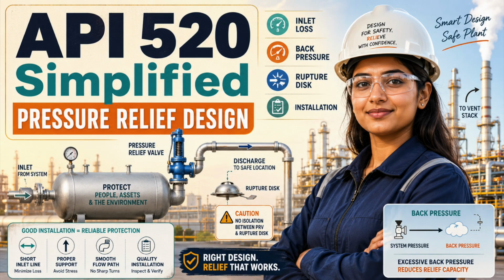When a rupture disc is installed upstream, its pressure loss must also be included. The inlet pipe should not be smaller than the valve inlet connection, but nominal size alone does not guarantee good performance. A same-size line can still be too long, too restrictive, or badly configured.